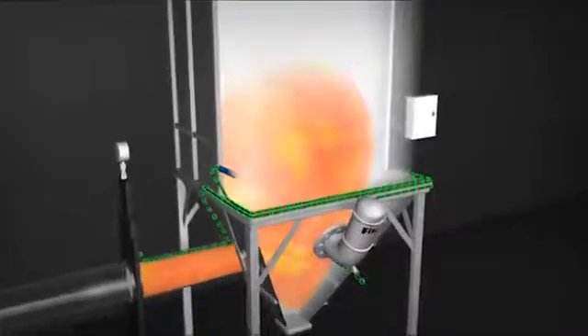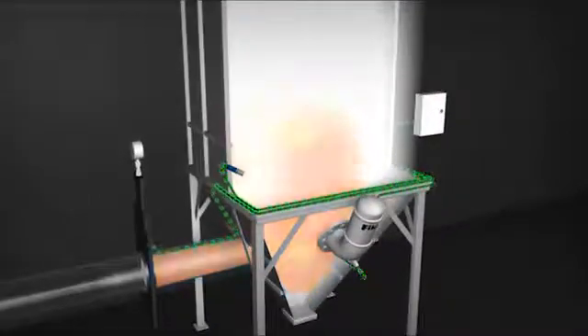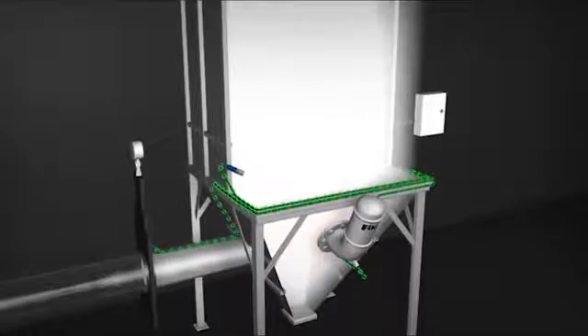The actuator opens a rupture disc on the suppressor bottle that uses nitrogen pressurized to 900 PSI to drive suppressant into the vessel, filling the entire cavity and extinguishing the advancing deflagration.